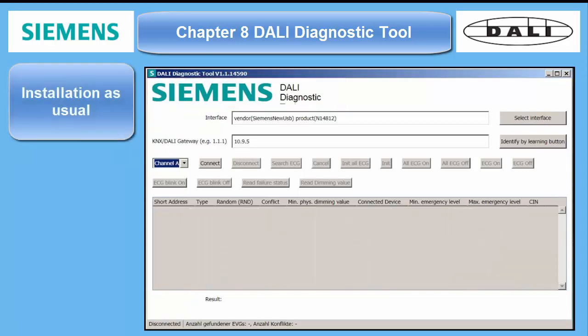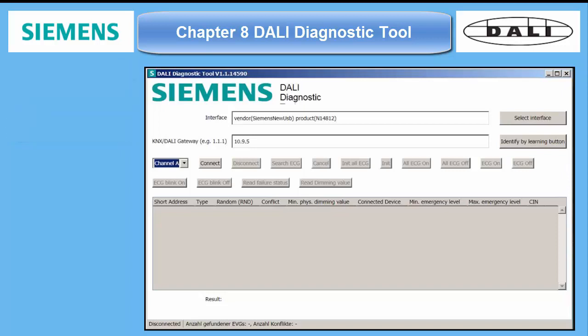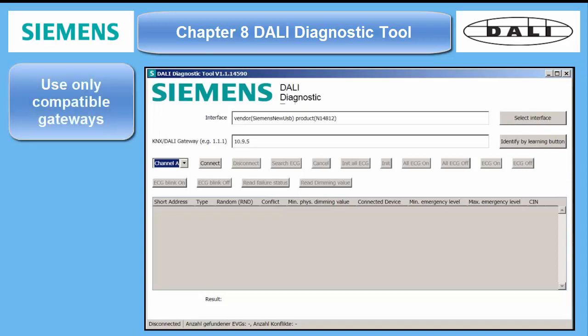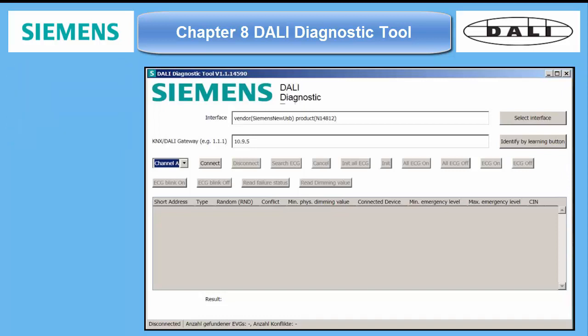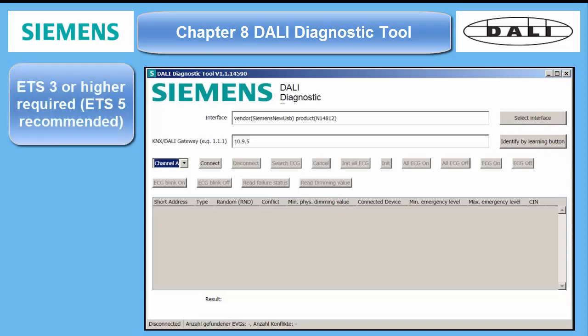The Siemens DALI diagnostic tool must be installed as usual. After installation, you start it and see the main page. Communication with the DALI bus always requires one of the previously mentioned compatible gateways. Since these gateways only have two access interfaces — KNX and DALI — the external access point is KNX. All available KNX bus interfaces can be used. Make sure you are also running ETS 3 or higher on your PC, because of the interface driver called Falcon.